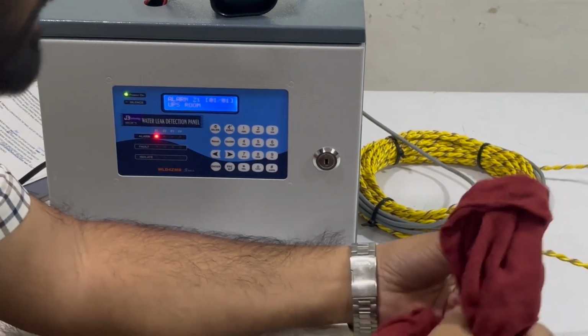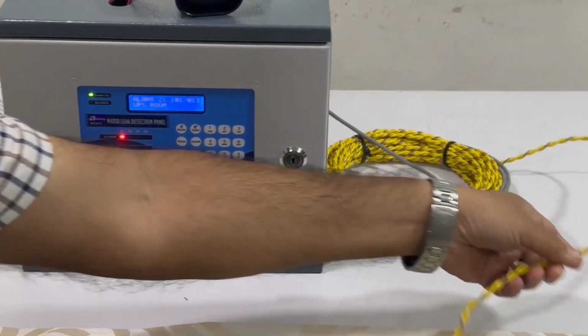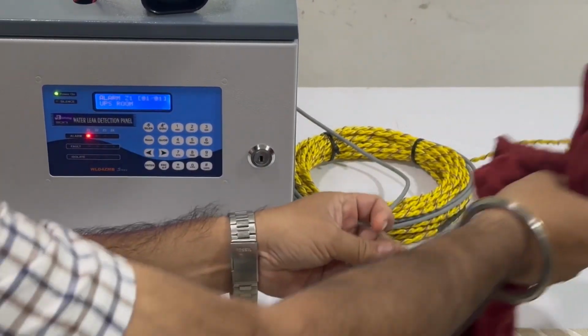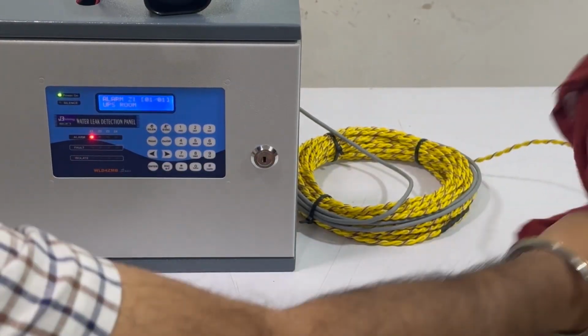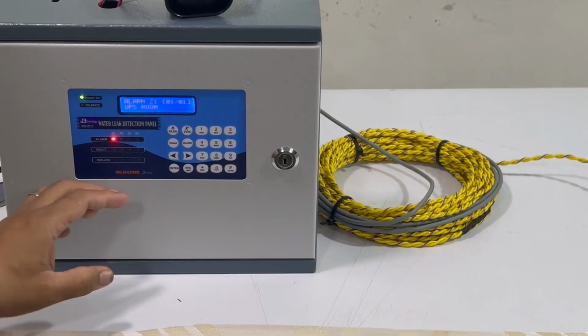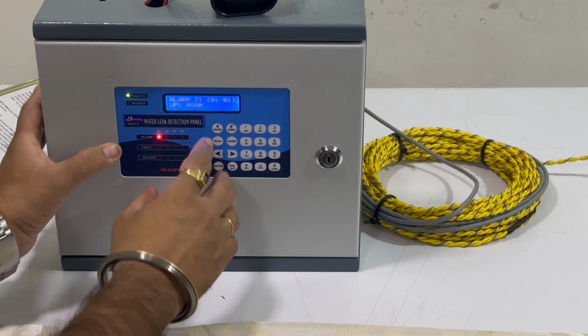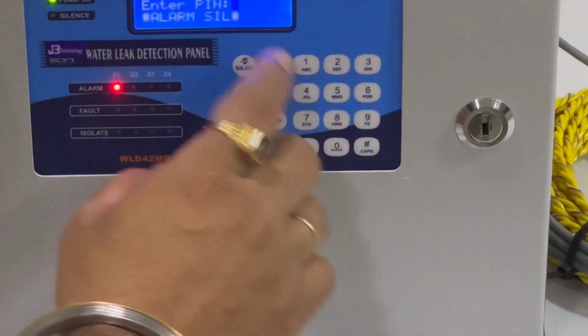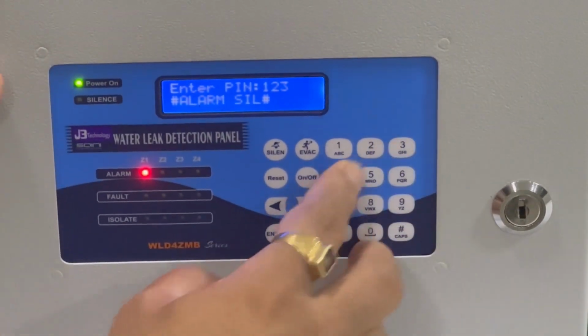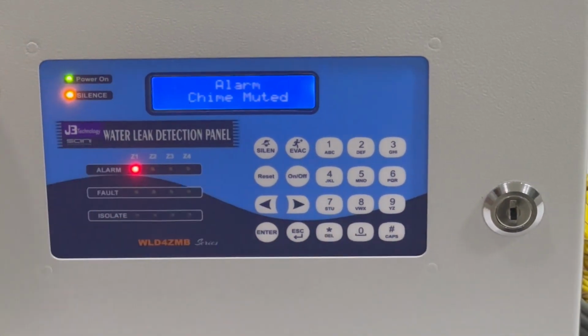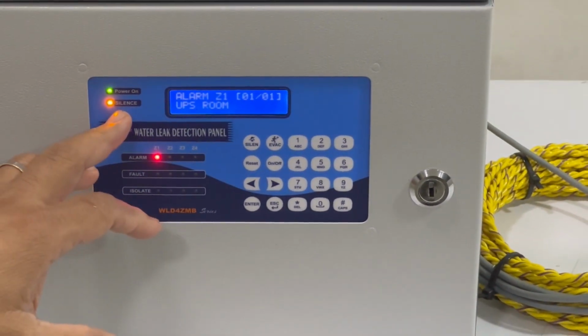Even on normal, just touching my right hand to the sensor cable will generate an alarm. It is a very high sensitivity. I have kept the panel on the high sensitivity. Now you can silence the panel. For silence, it will ask for the password. 1, 2, 3, 4. The panel is silenced. You can see the silence light is on.